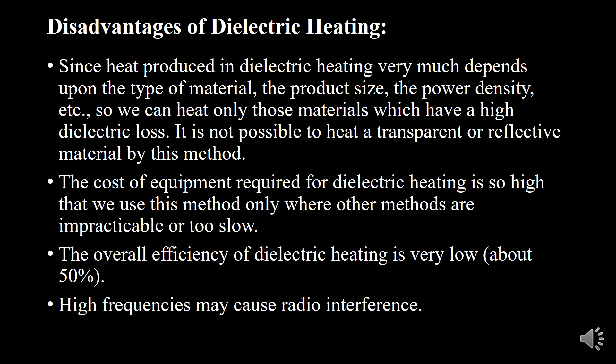Disadvantages of dielectric heating: the heat produced depends very much upon the type of material, product size, and power density, so only materials with very high dielectric loss can be heated. It is not possible to heat transparent or reflective materials by this method. The cost of equipment is high, so this method is used only where other methods are impractically slow. The overall efficiency of dielectric heating is very low, about 50 percent, and high frequencies may cause radio interference.